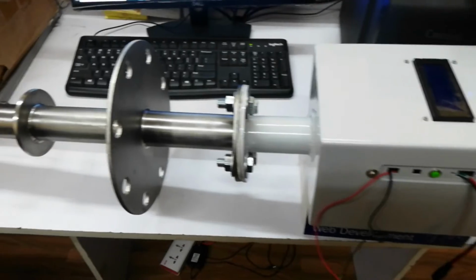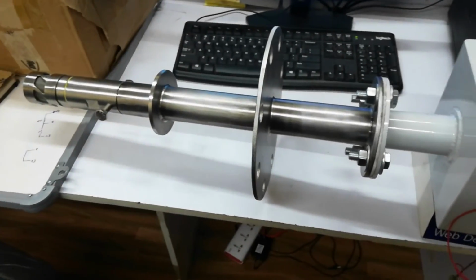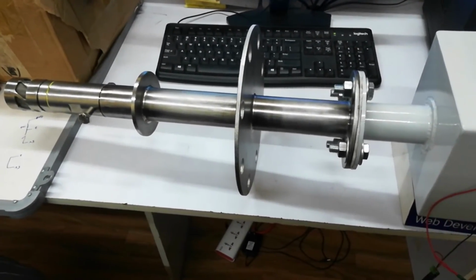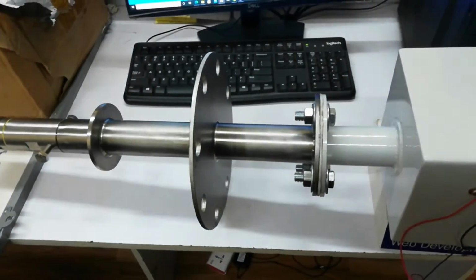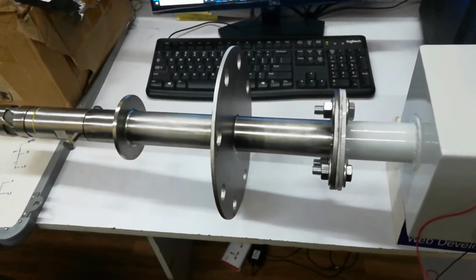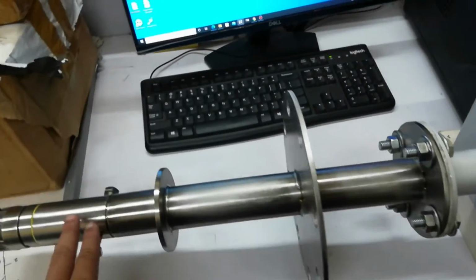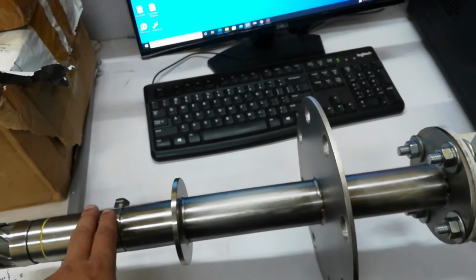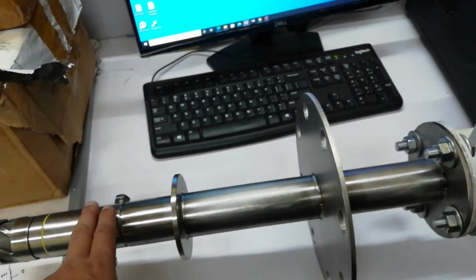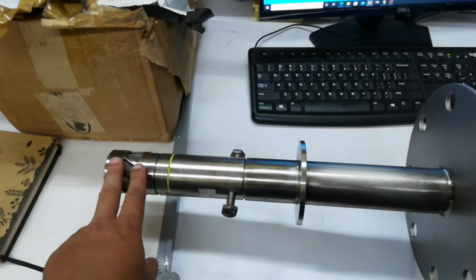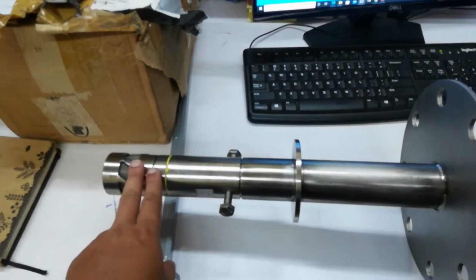This is the body of the oxygen analyzer. So you see the big flange over here, which will be used for mounting it onto the duct. And here you have one thermocouple inside, which will measure the temperature of the flue gas. And inside here you have the oxygen analyzer sensor.